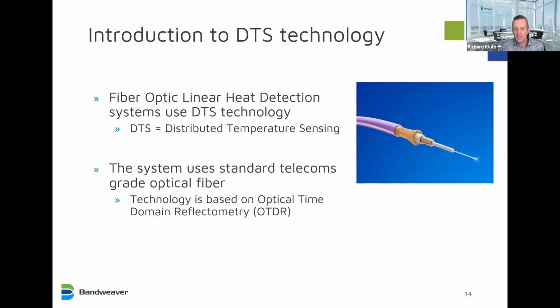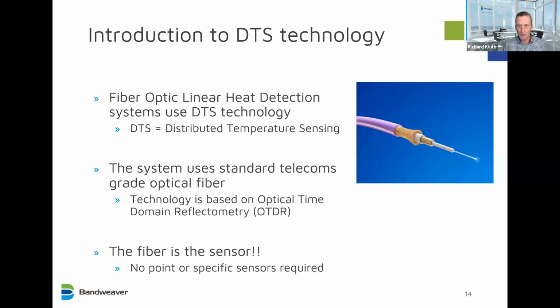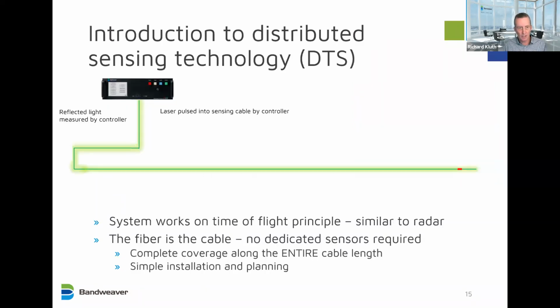But what distributed temperature sensor really means is the system uses standard grade telecoms fiber, and it uses something called optical time domain reflectometry, or OTDR, which is a bit of a mouthful, but as we'll see in the next slide, is basically very similar to time of flight for radar, but using light. But the key takeaway at this point is that the fiber is the sensor. You don't need any specific points, you don't need any engineering. The fiber does it itself. And I'll show you how.